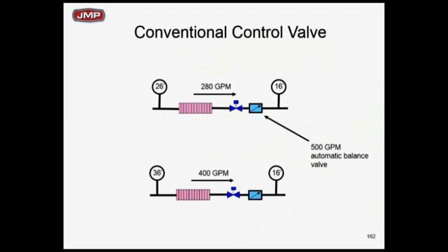I have the same setup as before, a standard two-way valve. I have a flow limiter picked for 500, but I'm running at 280 GPM. My two-way valve is partially closed. I have a partial load. I have 10 feet of drop and I'm running at 280 GPM. Everybody's happy. What happens if this differential pressure changes again to 20 feet, like we did in the previous example? The two-way valve is going to jump up to 400 GPM again. I'm going to lose delta T control because that PIC valve is not here. You have a regular two-way calibrated valve.